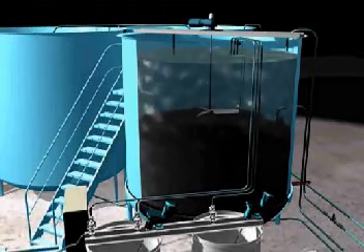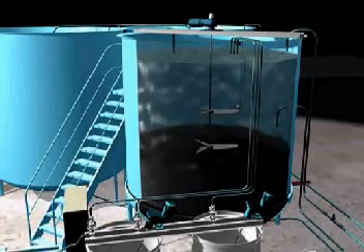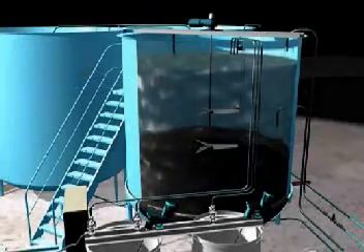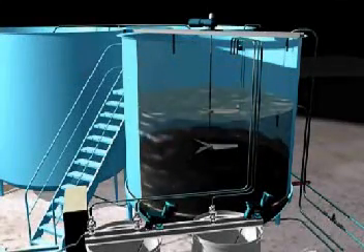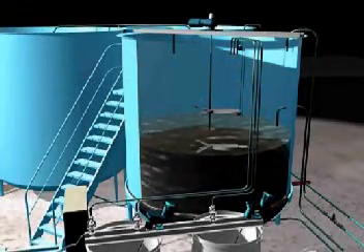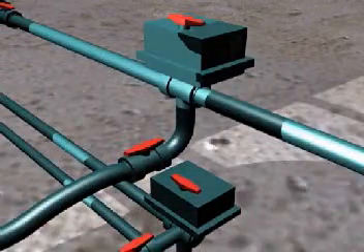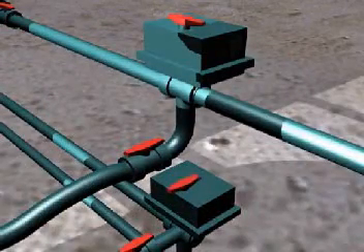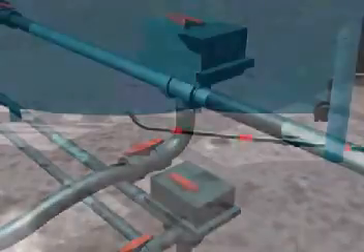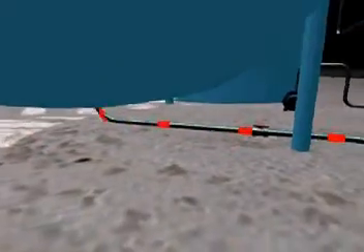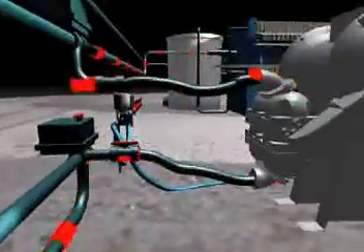The system then begins the settling phase, where the floc, now called sludge, settles to the bottom of the treatment tank. Once the settling phase is complete, the system transfers the clarified water to the filter press. This stage ends once the water reaches the mid-float level sensor, which activates the phase of sludge transfer to the filter press, starting with the activating of three-way valves that allow the pump to draw sludge off the bottom of the tank and transfer it to the filter press.